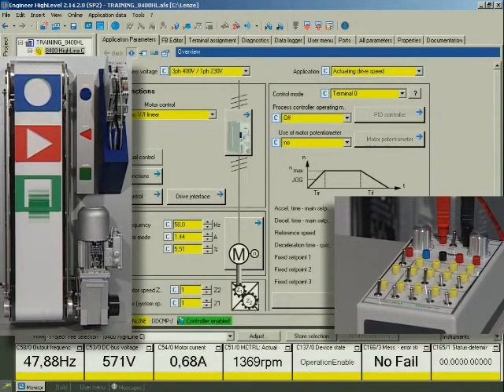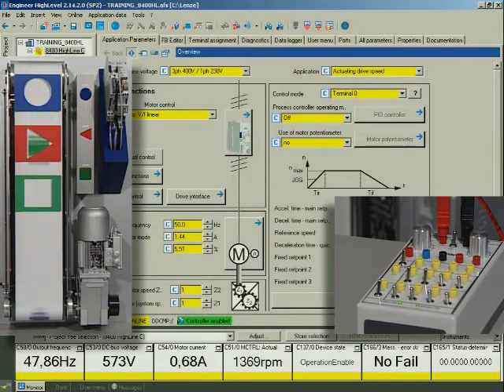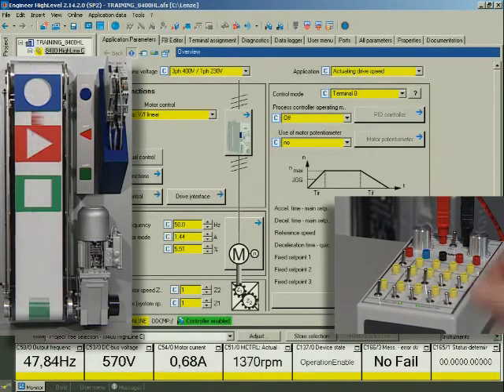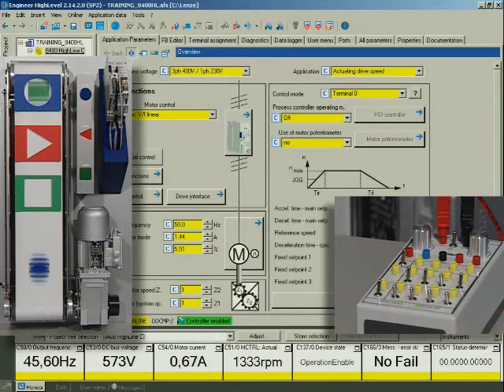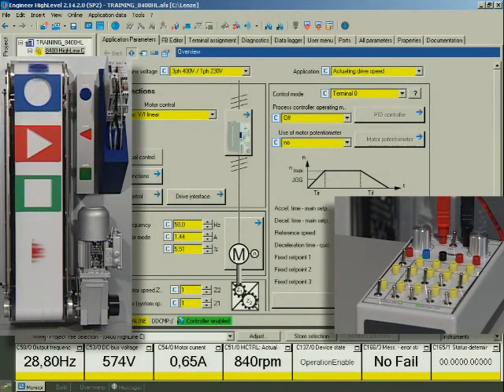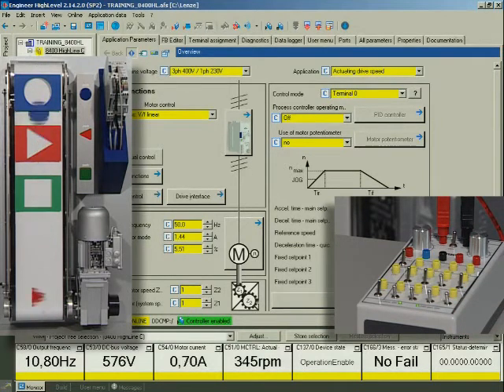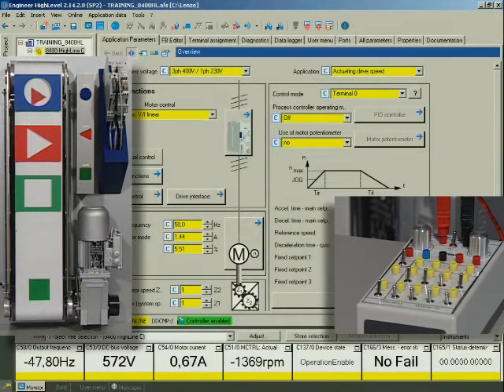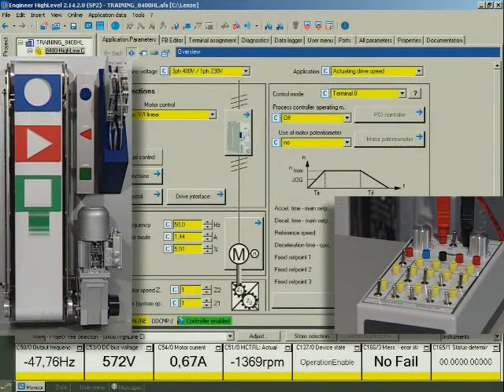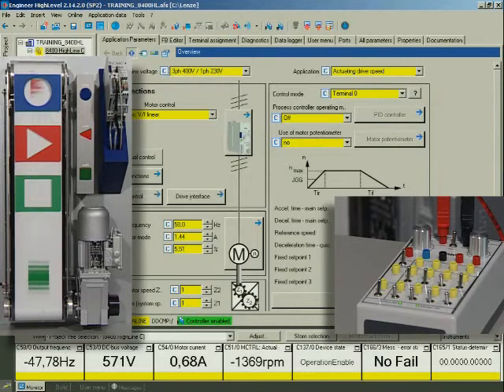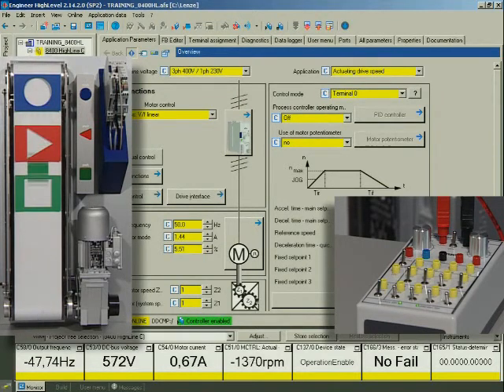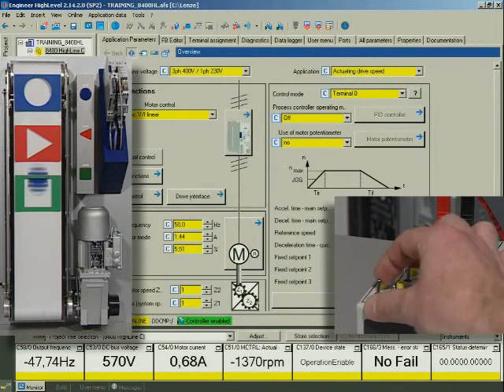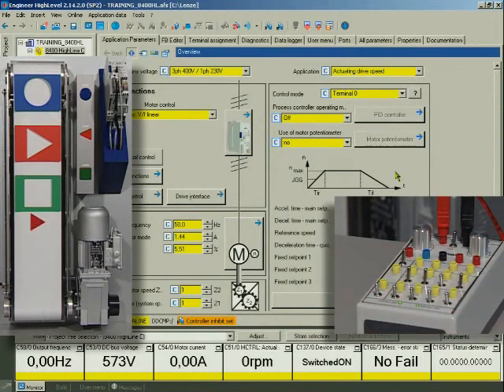Via digital input 4, we switch over the direction of rotation. The drive brakes to zero speed at the quick stop ramp and changes the direction of rotation. At the acceleration ramp, it accelerates to the speed set. The drive now rotates in the other direction at fixed speed 3. We are setting controller inhibit to stop the drive.